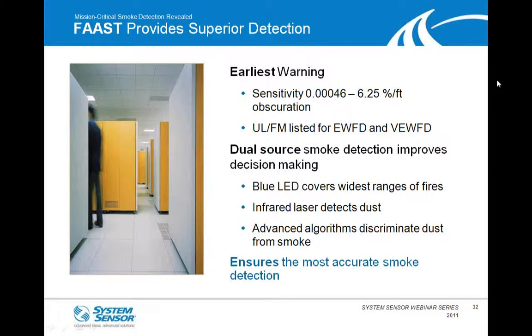And with the advanced algorithms between these 2 sources, we're able to do a much better job of determining whether or not we have a smoke condition or a combustion condition or a dust-based condition. Basically what this does is just provides more accurate smoke detection in these mission-critical facilities.